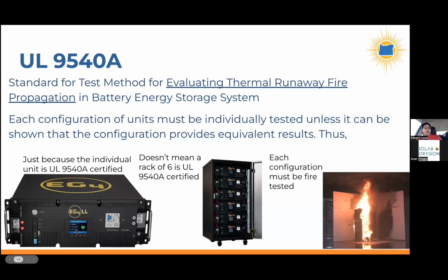So the UL 9540A test is a way of evaluating thermal runaway fire propagation. And so with this test, as you can see in the far right picture, there is a chamber and a setup, and how this test works is they disable any battery management system. They deliberately overcharge one cell in the module. In addition, they also have an ignition source: basically a little torch or an open flame near the cell that they forced to overcharge, to ignite any gases that come out of it and get the fire going. And then the test looks at how that fire propagates throughout the pack.